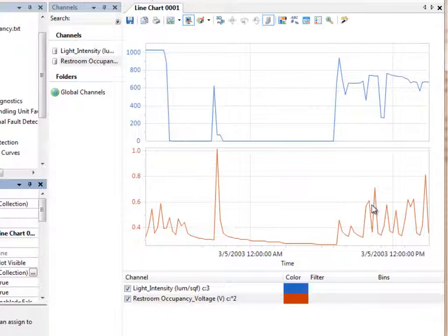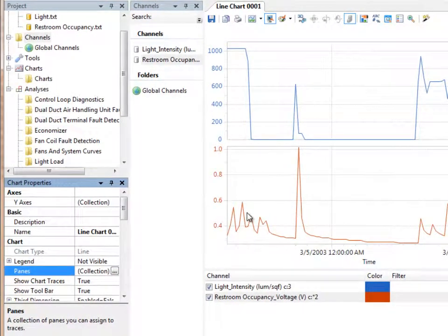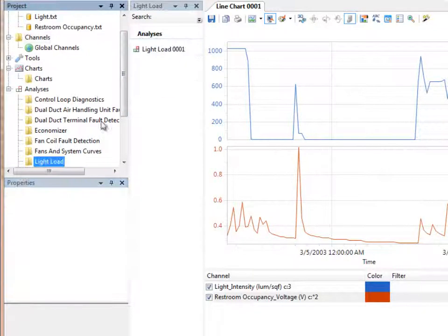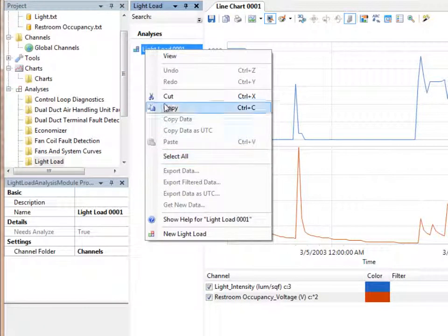In real life, I would want to make sure that I do some testing first with the occupancy sensor, because they do tend to be quite sensitive, and depending on how they're configured, I could get false readings from someone walking through a corridor as far as 20 feet away that triggers the occupancy sensor. Obviously, I wouldn't want that to then turn on the lights in the bathroom all the time. That's a little bit of field calibration that has to be done to get an understanding of how exactly this sensor is configured. But let's say we triggered this at about half a volt, and that would turn on the lights. How would that react in terms of energy savings if I were to actually connect that to a control system? So let's start an analysis here.